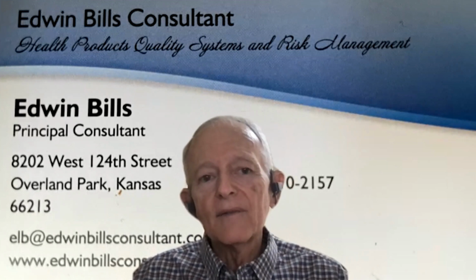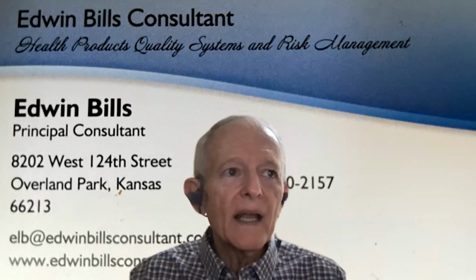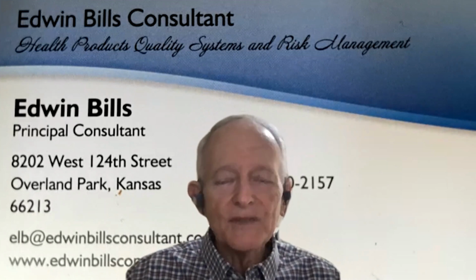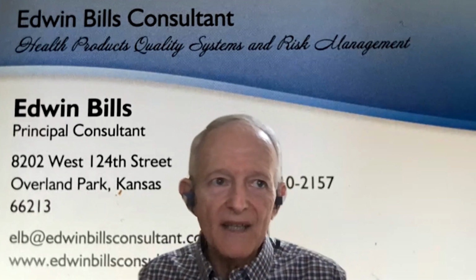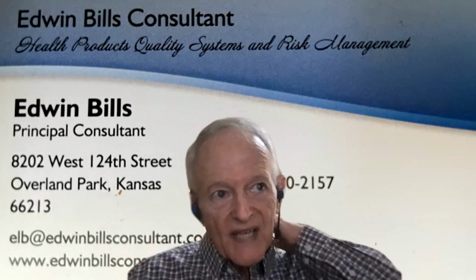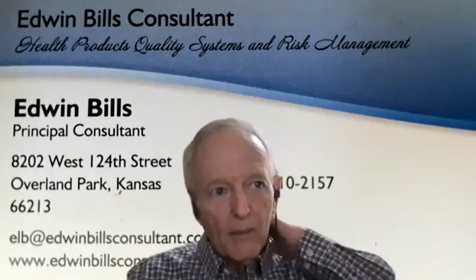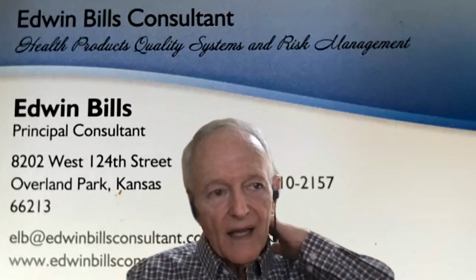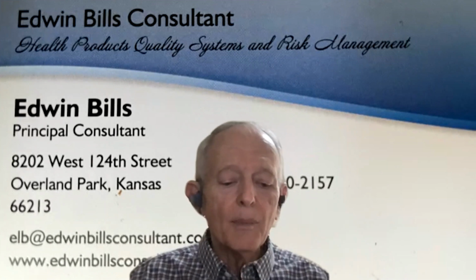And one of the things people overlook is that a lot of the standards, especially those considered state of the art, have already identified a lot of hazards and have proposed risk controls for those hazards and have proposed testing that you can perform to show that you have addressed that properly.